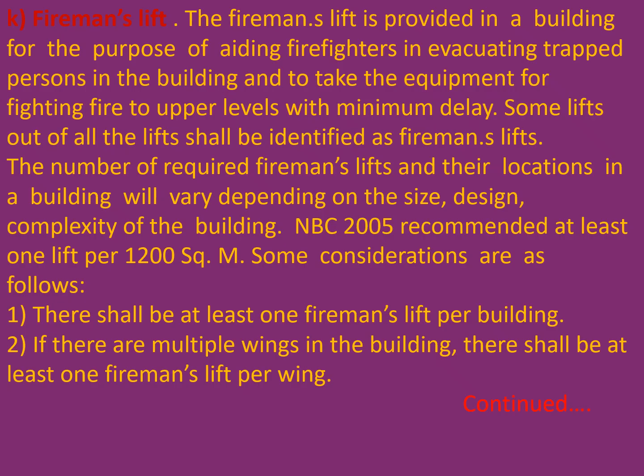National Building Code 2005 and 16 recommended at least one lift per 1200 square meter. Some considerations are as follows. 1. There shall be at least one fireman lift per building. Second, if there are multiple wings in the building, there shall be at least one fireman lift per wing. This will be further continued.